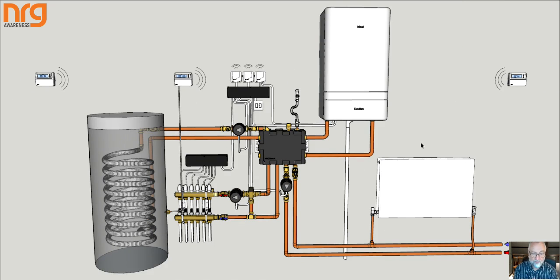So we've gone through it. We have the very unique boiler method that absolutely improves the way the water is being used by the system to maximize the delta T drop from flow to return on the boiler. And because the boiler has by far better input potential, data input potential, it can make much, much more accurate decisions. So not only is it by far simpler to install, it has the added benefit of the one amp fuse protection on every zone, the LED indication telling you what's going on, the very simple configuration because every terminal is already pre-identified with being earthed or a neutral or a permanent live or whatever. So very, very simple system.